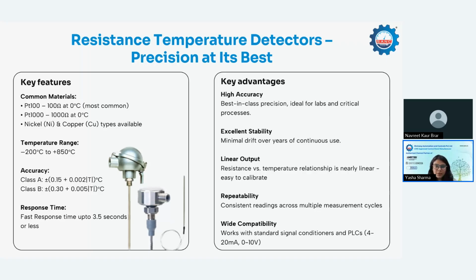Linear output. As I said, the resistance of the metal increases in direct proportion to the temperature. So the resistance versus temperature relationship is linear, which makes calibration very easy. Repeatability. In industrial processes, repeatability is a very important phenomenon to judge a sensor. So for consistent readings across multiple measurement cycles, you should go with RTDs.